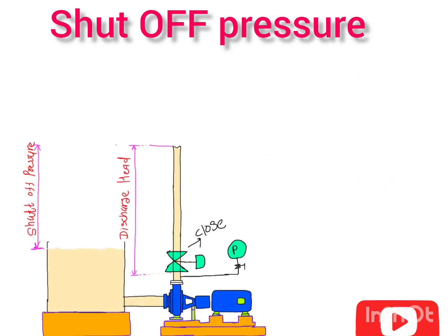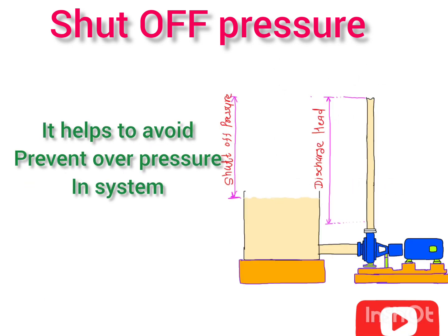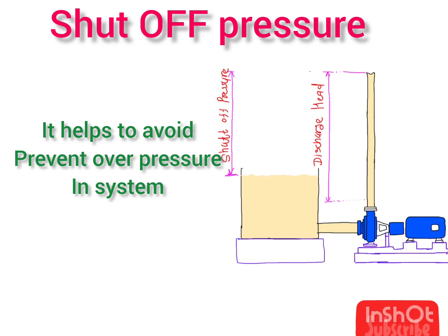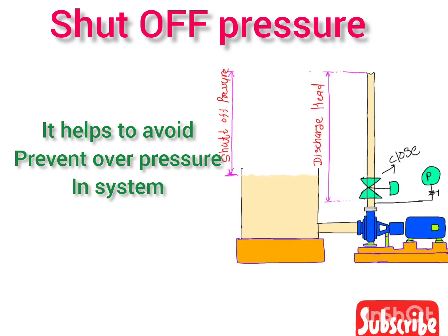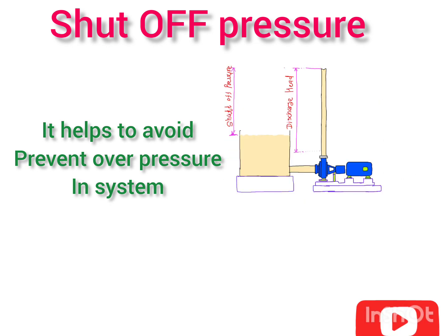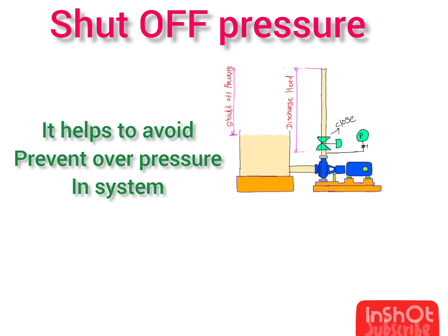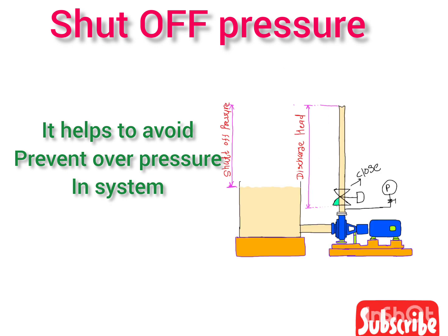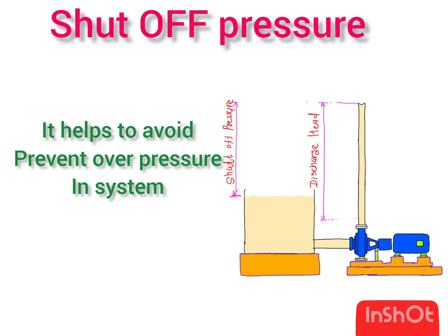The second benefit is that if you know the shut-off pressure, you can prevent overpressure in the system. For example, if you want 2 kg pressure in your system and you select a pump with a 2 kg shut-off pressure, then your system will not go beyond 2 kg pressure. So it helps you prevent overpressure in the system.